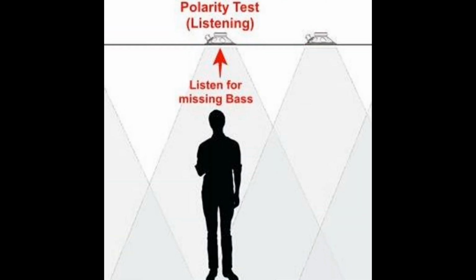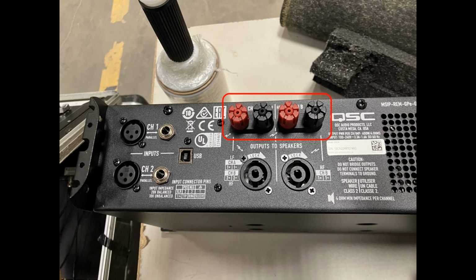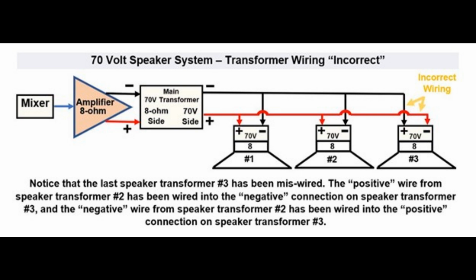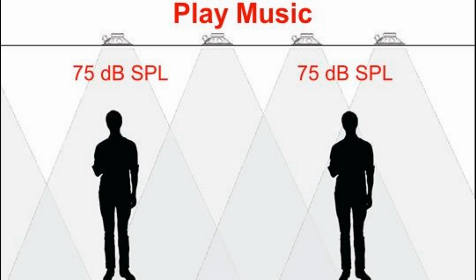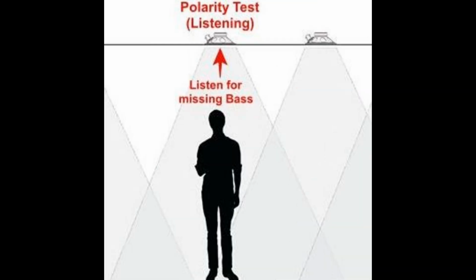The polarity check is similar to the tap value check. First, inspect the red and black wiring at the amplifier outputs for any mistake. Then, play a familiar music soundtrack and walk the zone, listening for missing bass frequencies under each speaker. If bass is missing, the polarity is most likely backwards for that speaker. Again, detection can be subtle, so take your time while walking each zone.